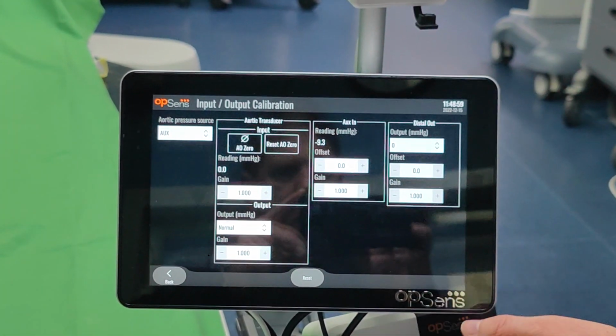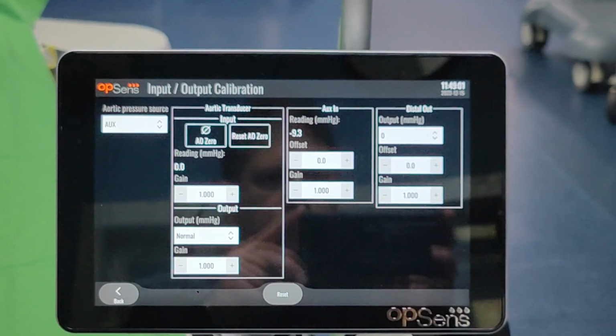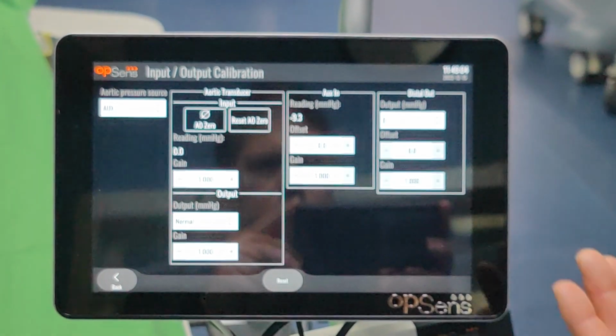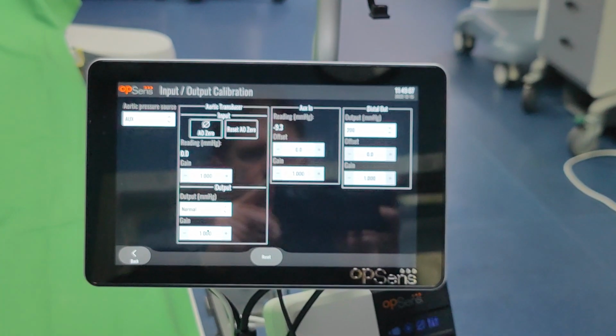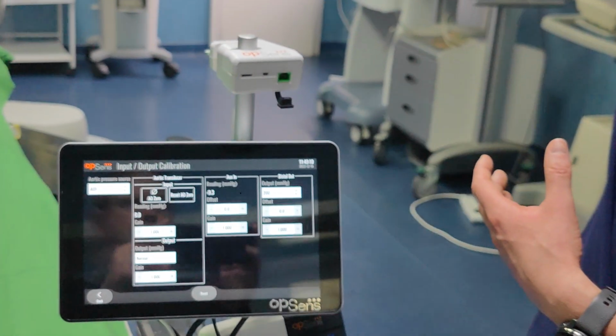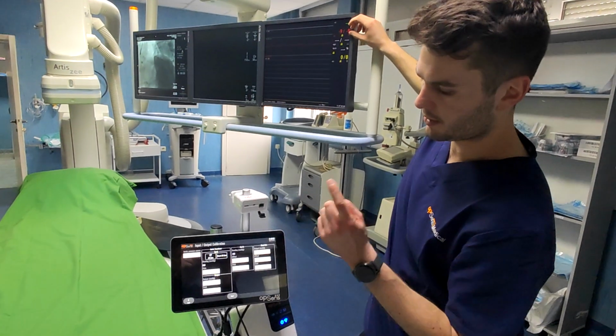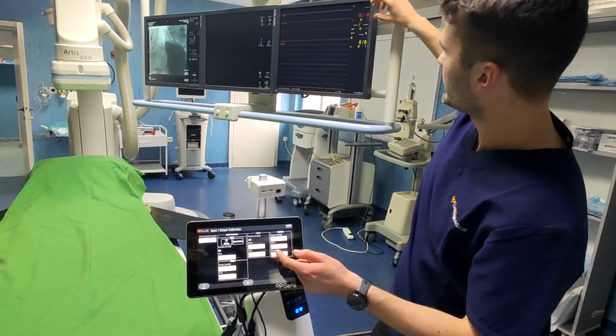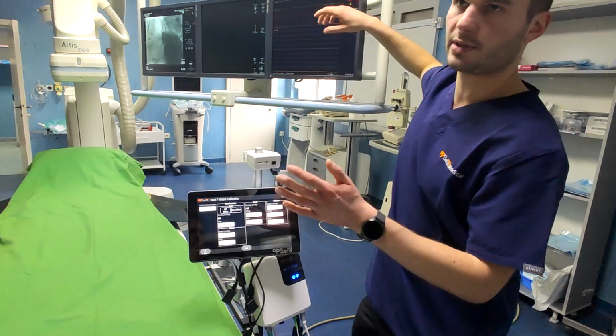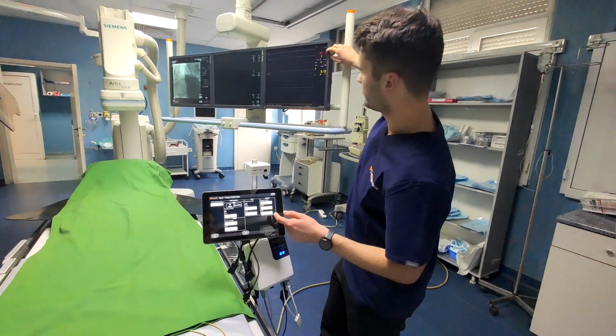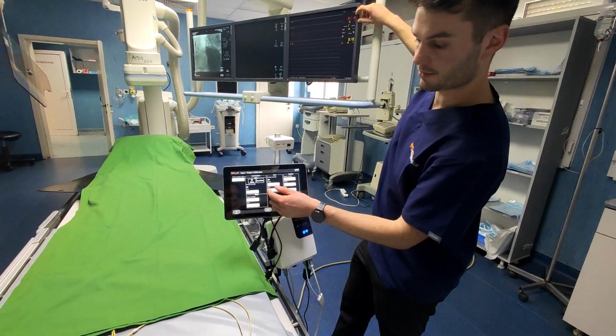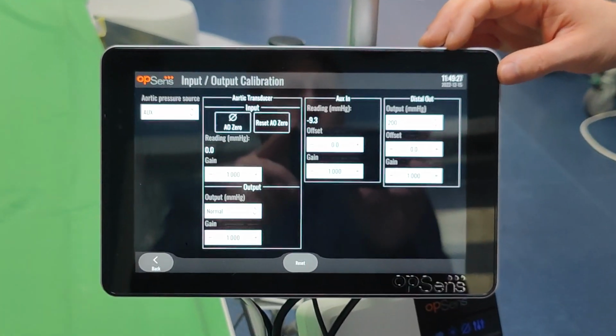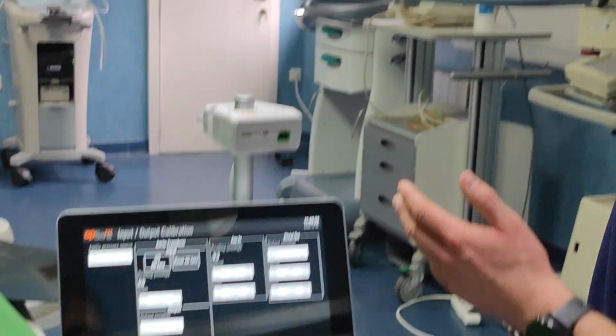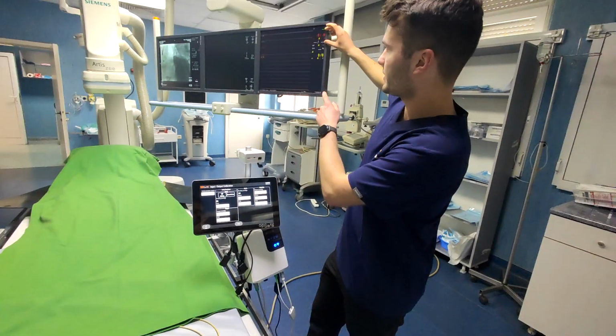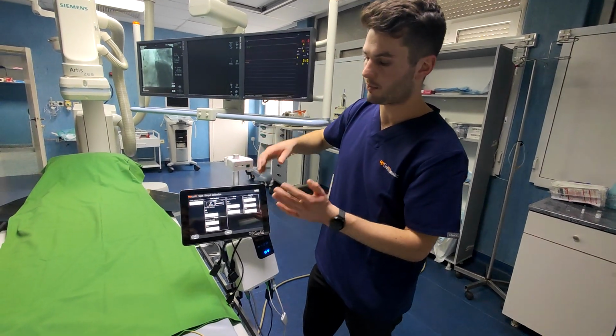The gain is the top end, so that's the higher number. So we set it to 200, which then sends a signal to 200 on here. You want this number to be the same as this number again. So whatever this number is, it could be 199, that's fine. You just want to match this number with this number on here, with the gain. And it's the same, up or down. So it could be that this is 198 from the 200 output. It doesn't matter if that's not 200. The main thing is you want this to match that, because that's where you're getting the signal from for the calculations.